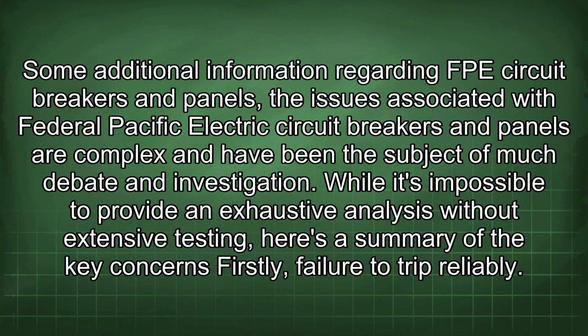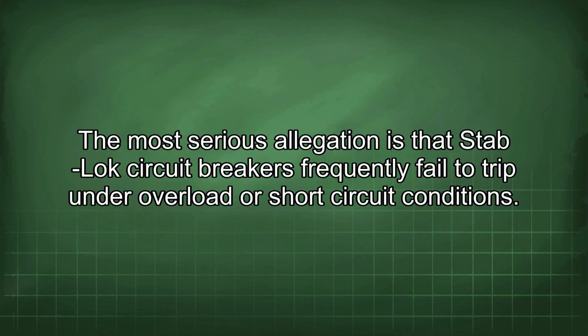Some additional information regarding FPE circuit breakers and panels. The issues associated with Federal Pacific Electric circuit breakers and panels are complex and have been the subject of much debate and investigation. While it's impossible to provide an exhaustive analysis without extensive testing, here's a summary of the key concerns. Firstly, failure to trip reliably. The most serious allegation is that Stab-Lok circuit breakers frequently fail to trip under overload or short circuit conditions.